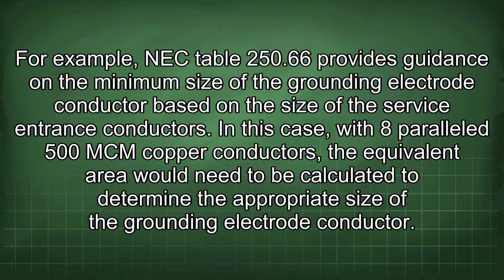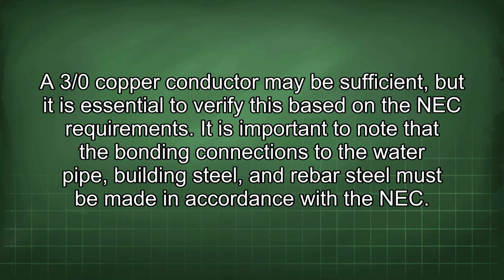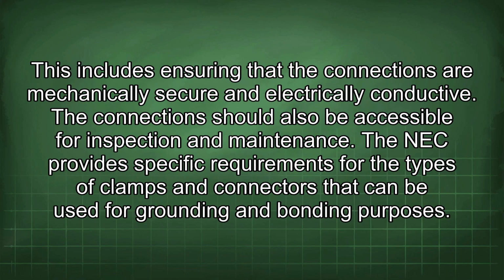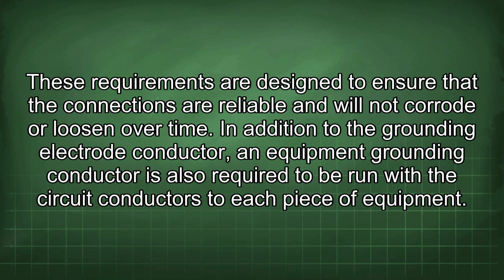In this case, with 8 parallel 500 MCM copper conductors, the equivalent area would need to be calculated to determine the appropriate size of the grounding electrode conductor. A 3/0 copper conductor may be sufficient, but it is essential to verify this based on the NEC requirements. It is important to note that the bonding connections to the water pipe, building steel, and rebar steel must be made in accordance with the NEC. This includes ensuring that the connections are mechanically secure and electrically conductive. The connection should also be accessible for inspection and maintenance. The NEC provides specific requirements for the types of clamps and connectors that can be used for grounding and bonding purposes. These requirements are designed to ensure that the connections are reliable and will not corrode or loosen over time.